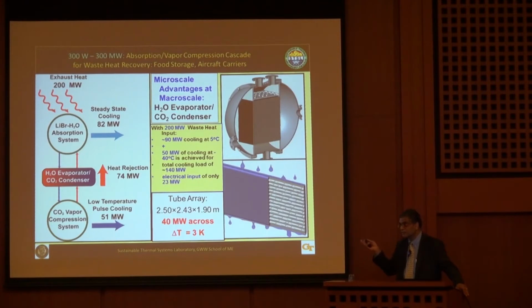So we're applying a conventional shell and tube heat exchanger concept, but the novelty here is that usually when you talk about micro-scale processes and micro-channel heat exchangers, you're thinking about electronics cooling, 5 or 10 watts. We've shown you can apply those same principles to very large systems, and because these systems are so large, you can really cut down the size.